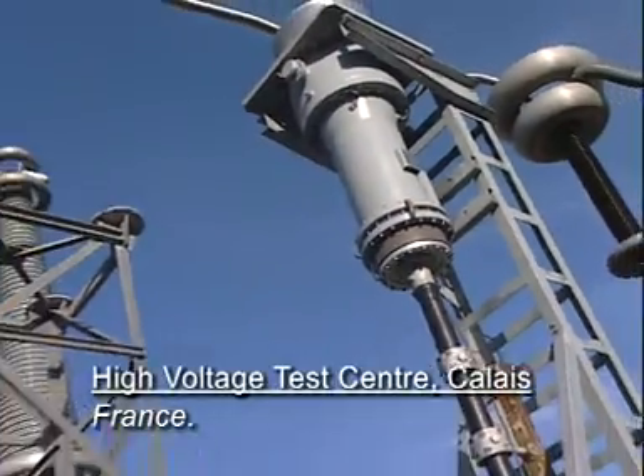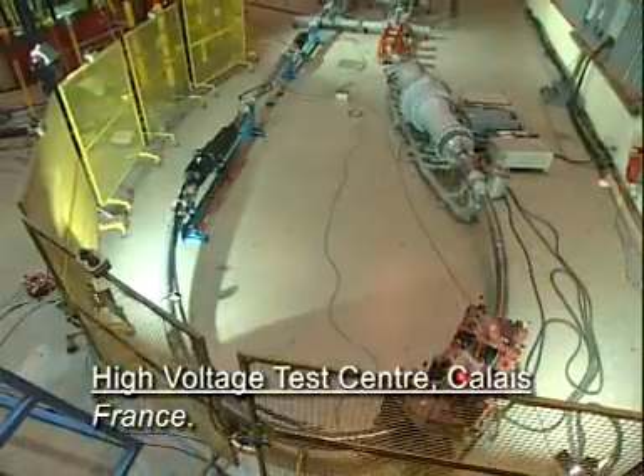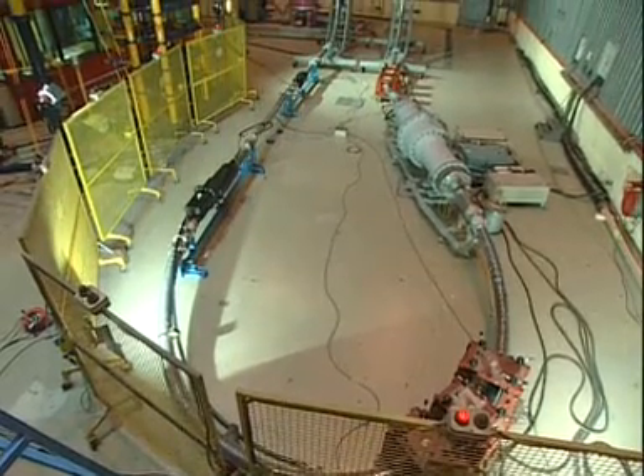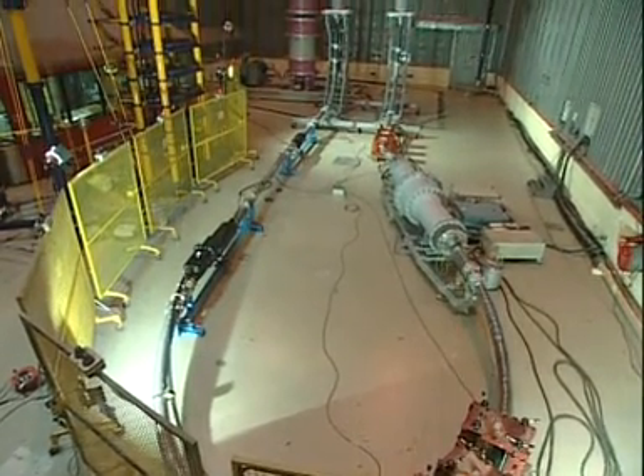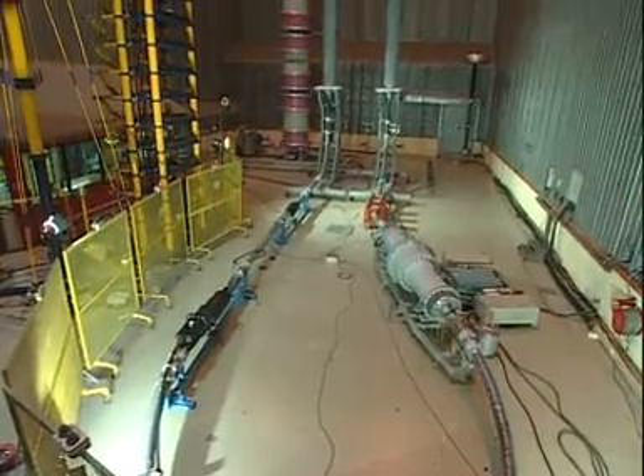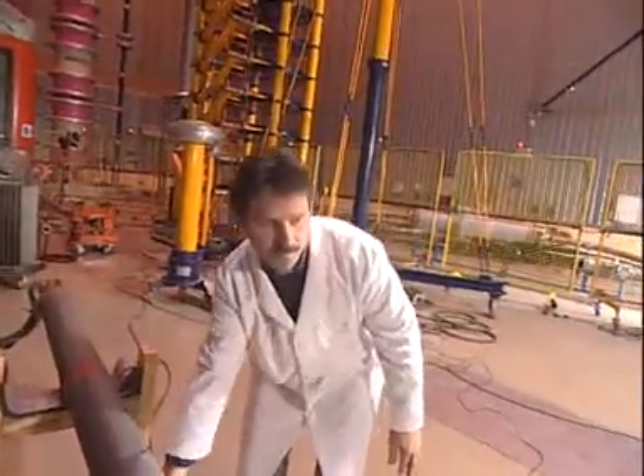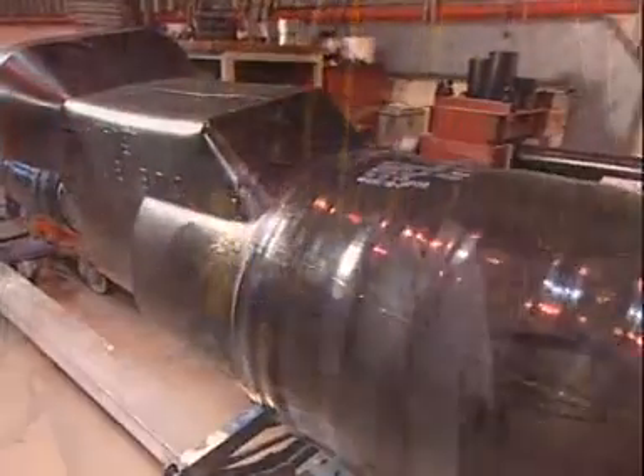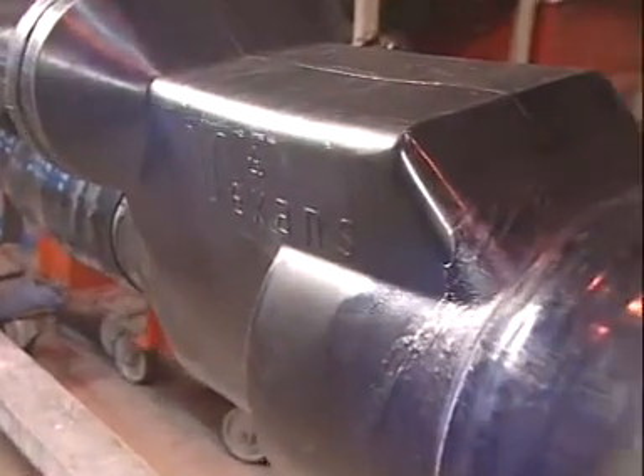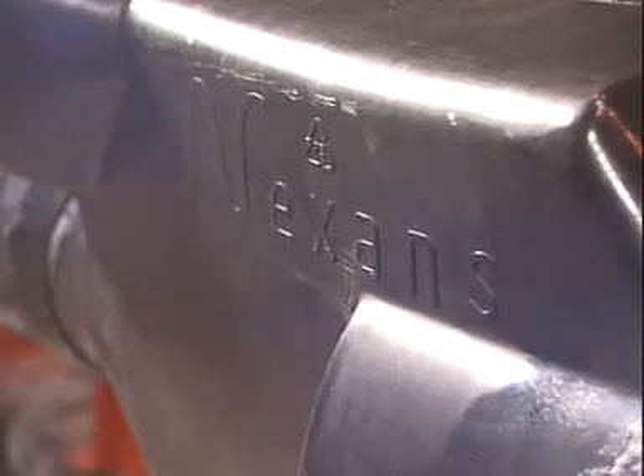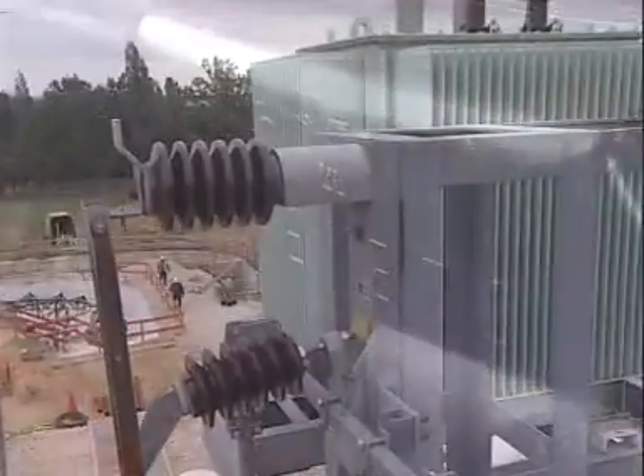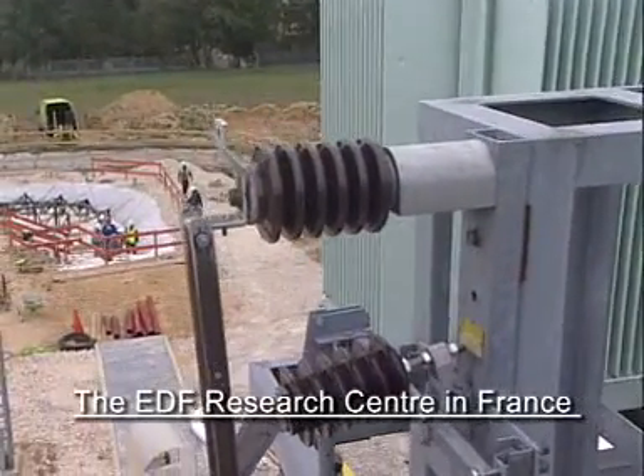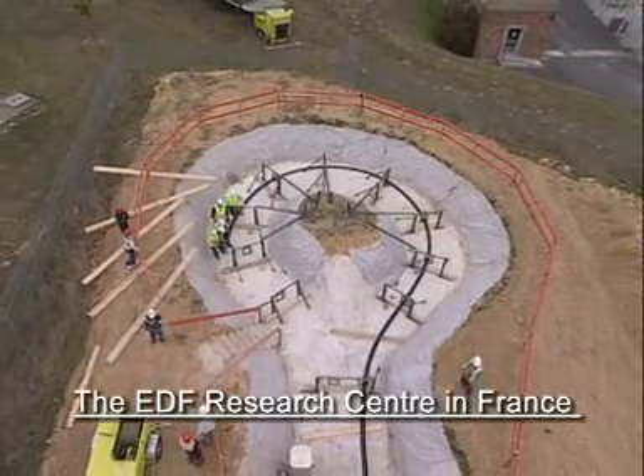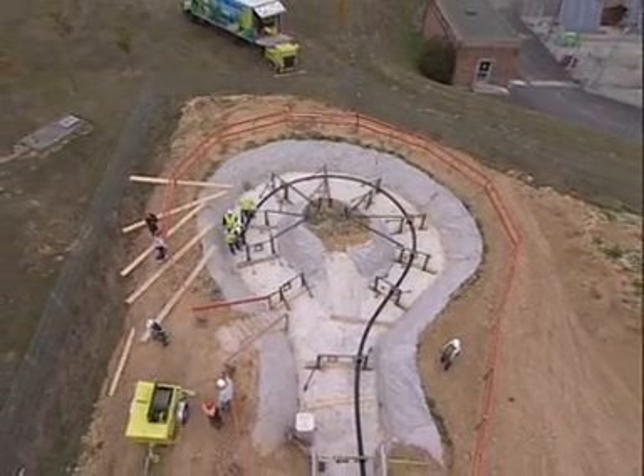Type tests were performed at the High Voltage Test Center in Calais, France. This is a test loop containing an accessory of each type, for example, one GIS end unit, one composite outside end unit, a joint with screen separation, and a straight joint. Long-term tests were conducted at the EDF Research Center in France on a 200-meter loop also containing a model of each type of accessory.